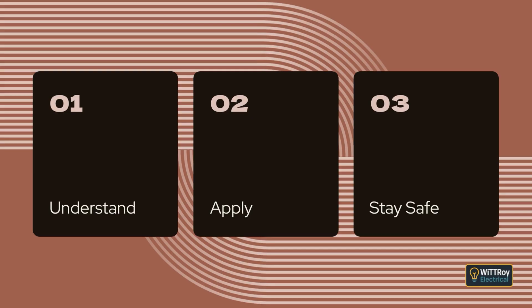Clause 1.6.3, Maximum Demand. The next step is maximum demand. The designer must work out the maximum current the installation is likely to draw under normal use. To do this, you consider the total electrical load, how the load is distributed through the building, and how the equipment is expected to operate.